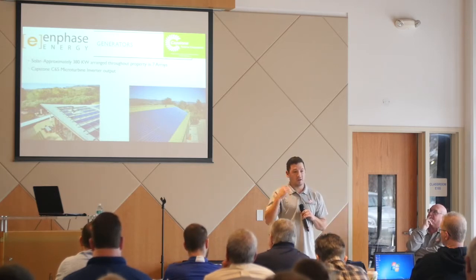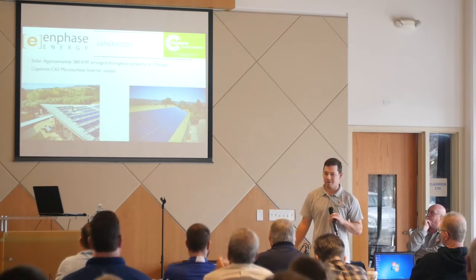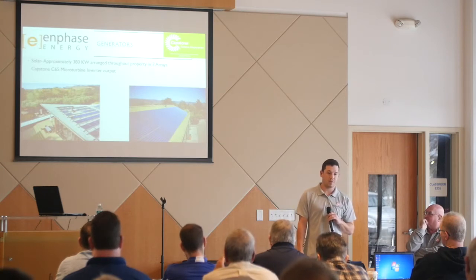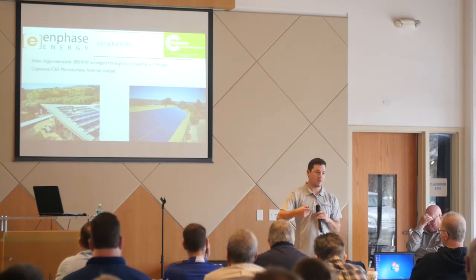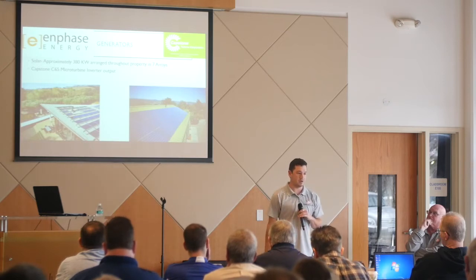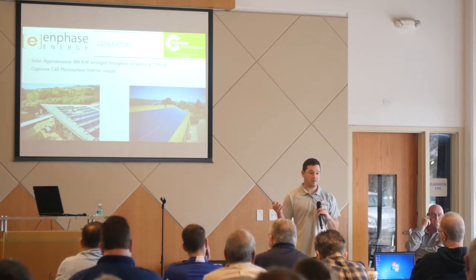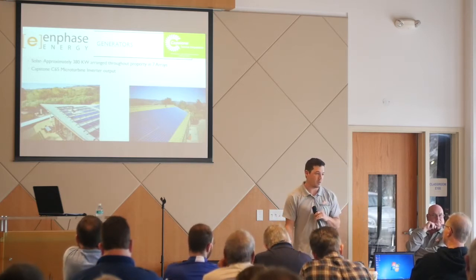So we've actually installed a tri-generation system, kind of like the one that Carlos showed in the pictures, not quite to the scale that they're using in Shanghai. But we've got a 10-ton Yazaki absorption chiller connected to our turbine. We're exploiting the waste heat coming off of it and collecting that in the form of hot water, storing it in tanks and running it through the chiller to create cold water as well, and distributing that through 2 spas and 6 buildings, I think. So that increases the efficiency of when we're actually needing to run on the Capstone when we're in the middle of the night. Maybe we need to charge some batteries.